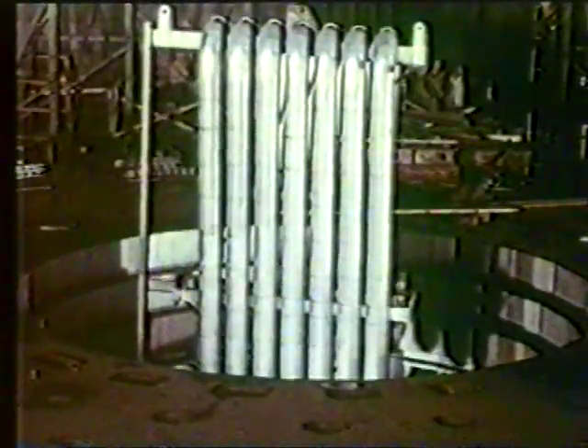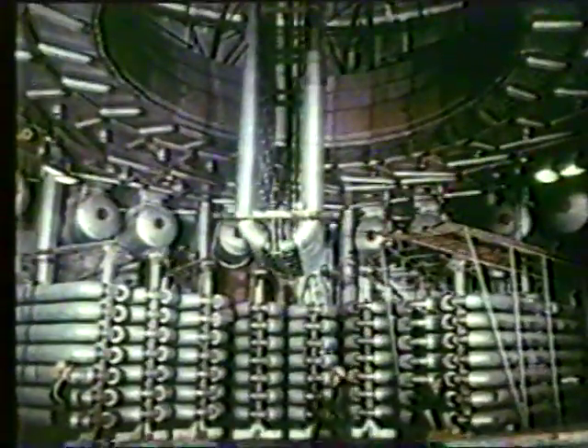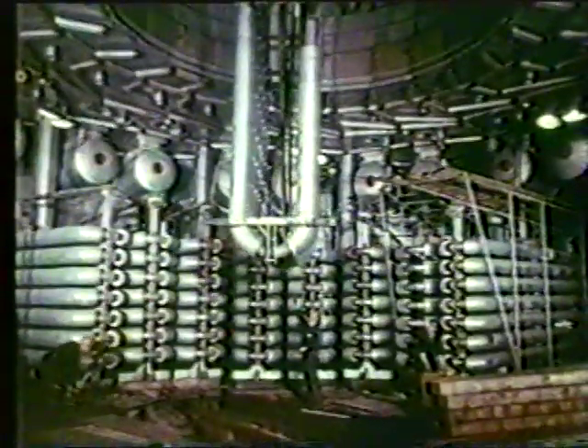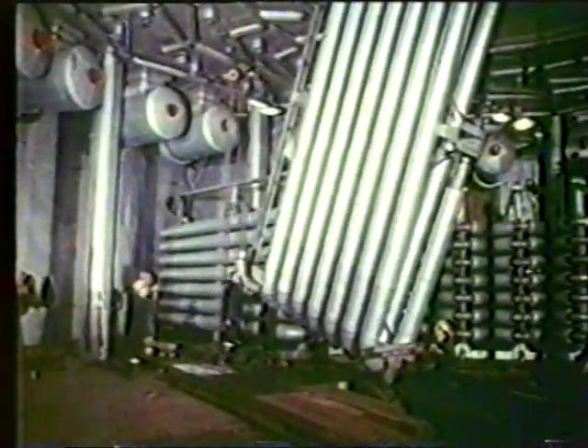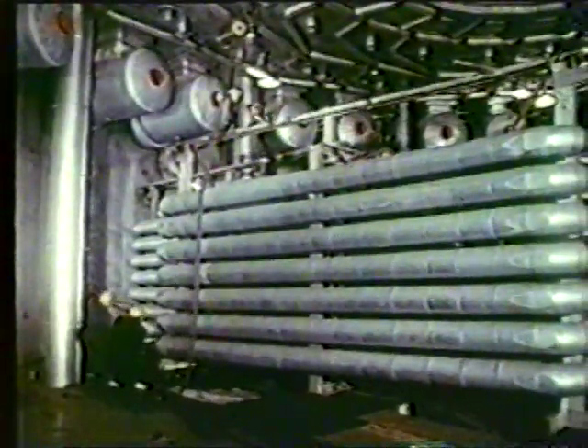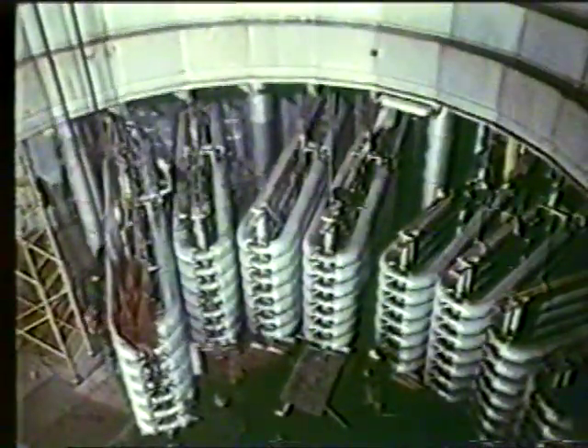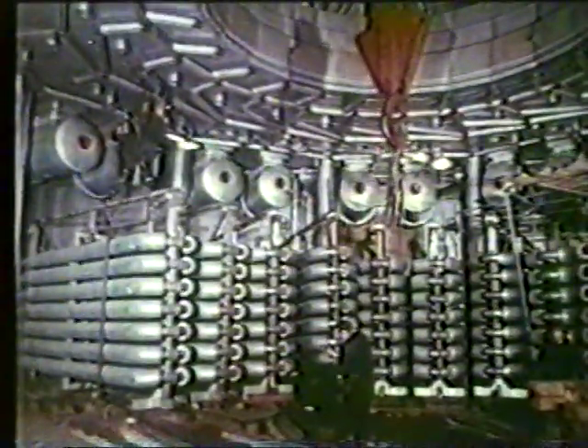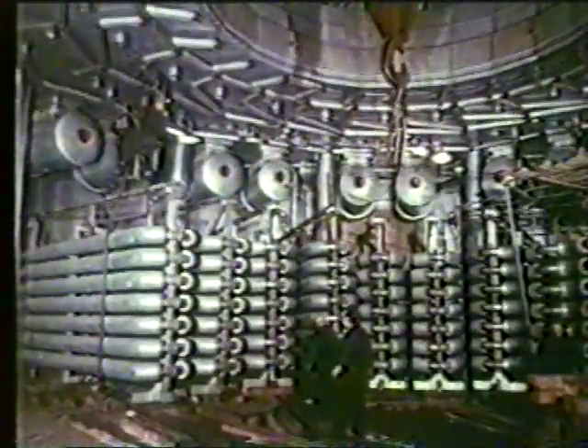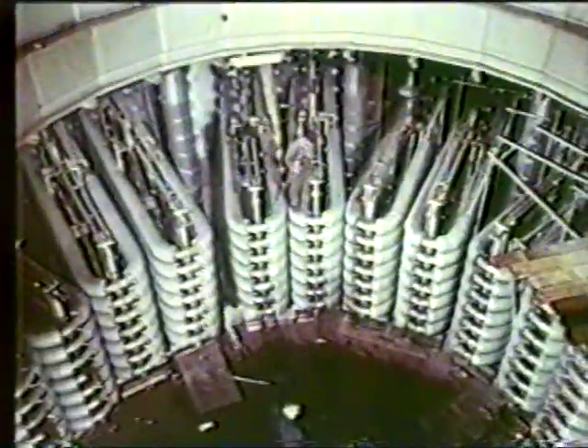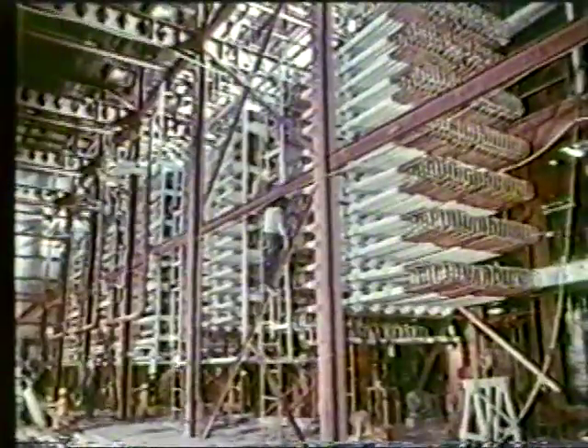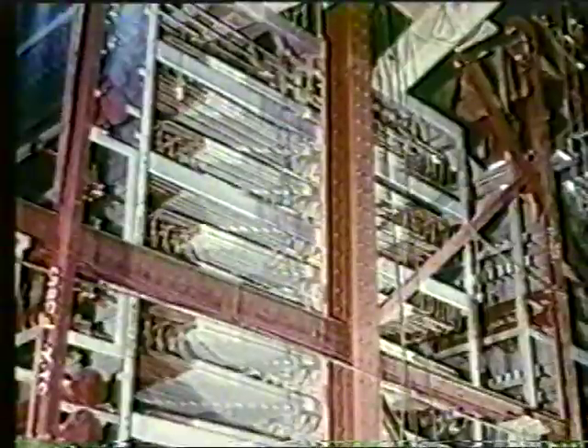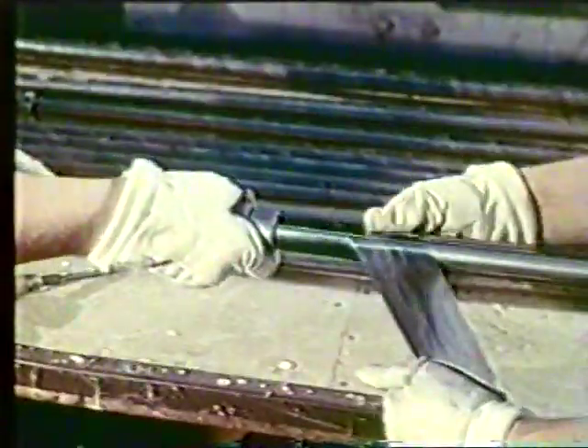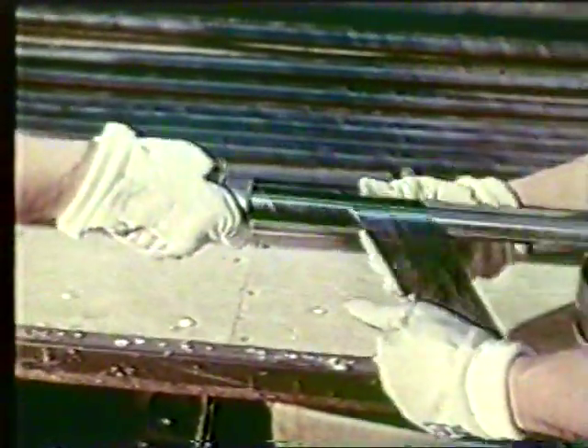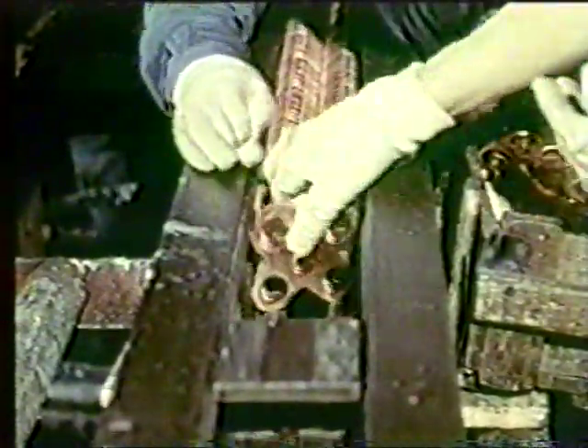The primary heat exchanger system consisted of 24 units in parallel. This was on account of the limited capacity of the pumps, but it also provided valuable protection against loss of coolant flow. These units each contain a central tube carrying the primary coolant, which gives up its heat to the secondary coolant flowing around it. This is also a liquid metal, but does not become radioactive. In the secondary system, the heat is transferred from the liquid sodium to water to raise steam. To avoid the possibility of a leak from one to the other, each unit consists of 5 separate tubes bonded together by copper laminations. The inner tube containing water and the 4 outer tubes, sodium.